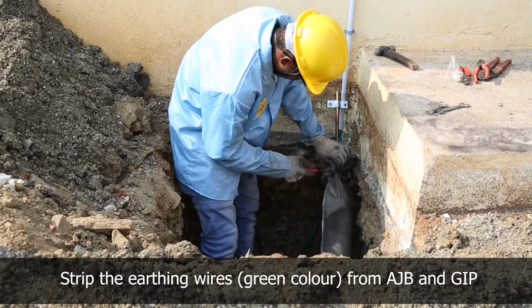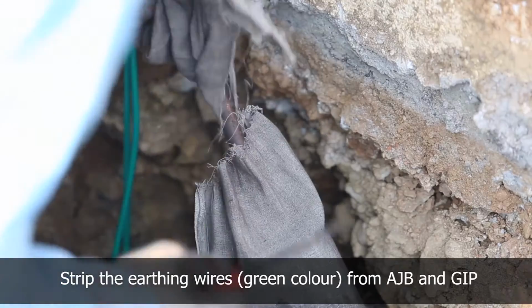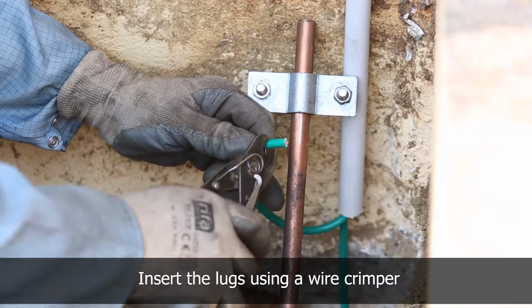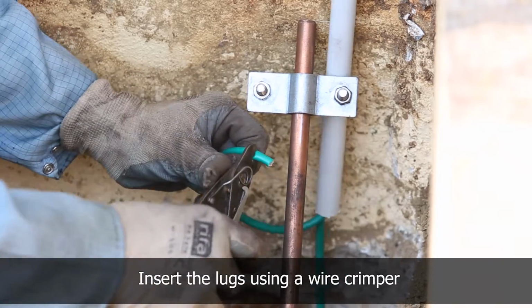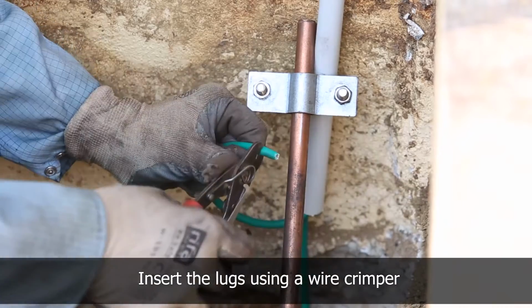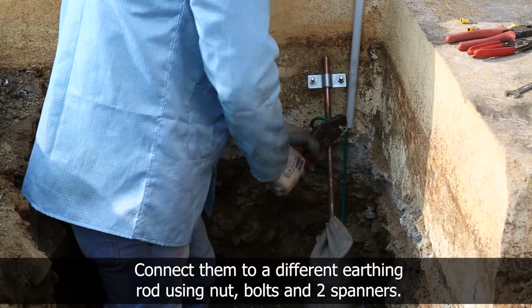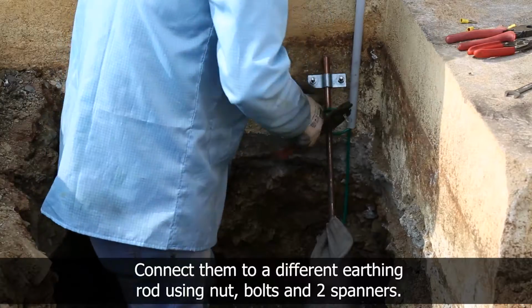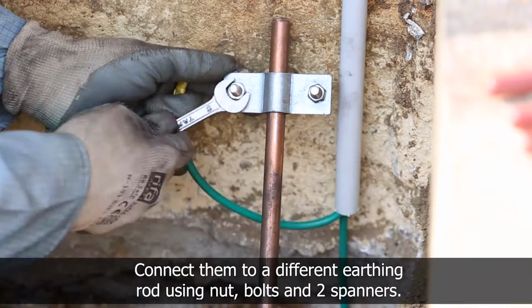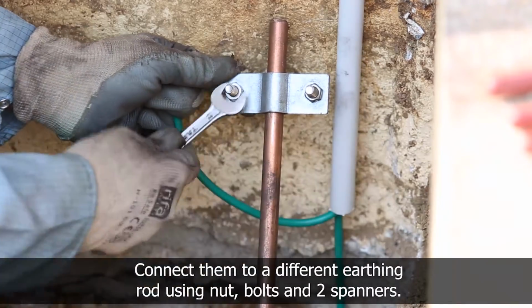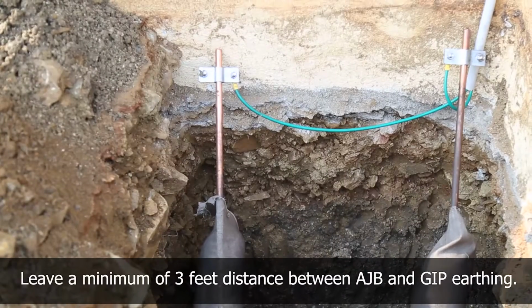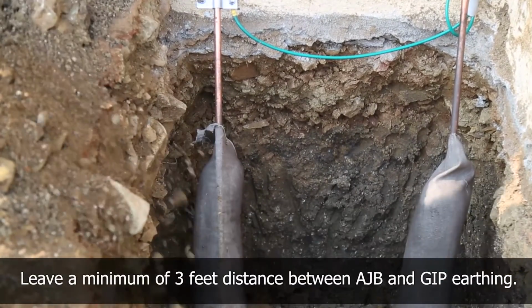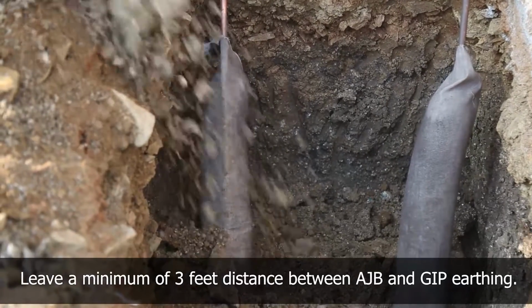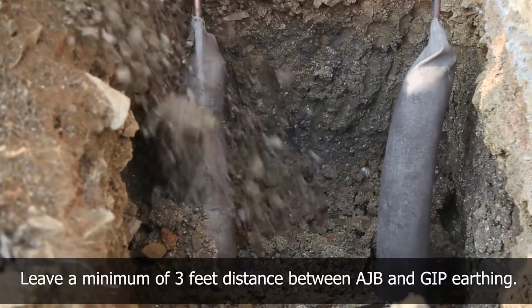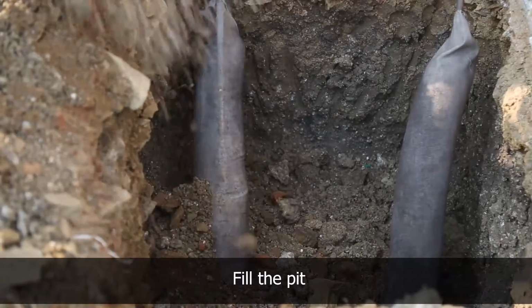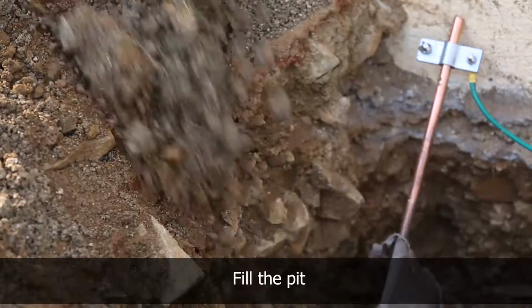Now, to do the earthing, dig 2 earthen pits of 1 foot by 1 foot by 3 foot and use the ready-made chemical earthing kit. Strip the earthing cable from the array junction box and the grid input protection box and connect it to the clamp of the earthing rod. Leave a minimum of 3 feet distance between the earthing of the array junction box and the grid input protection box and fill the pit with mud.